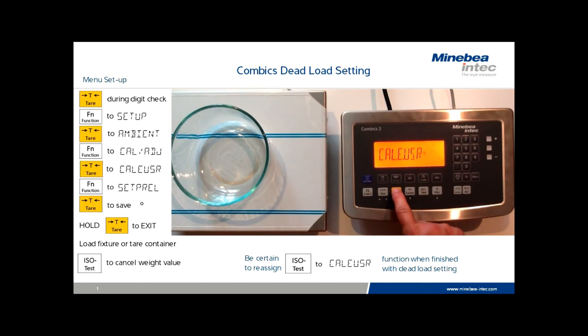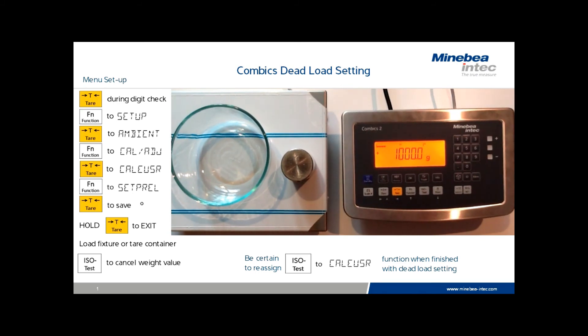Now that our user has enabled the Cal E user function, again we exit to the weighing mode and run one final calibration. Press the ISO test key, which is now back to its calibration function, place the requested test weight on the platform, and press the ISO test key to make a final correction. This concludes the dead load setup procedure for Combics indicators.